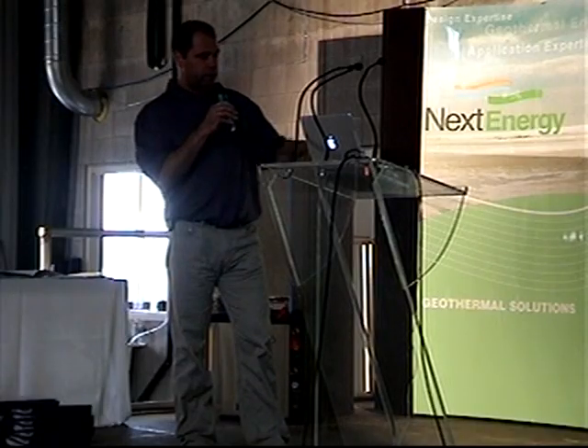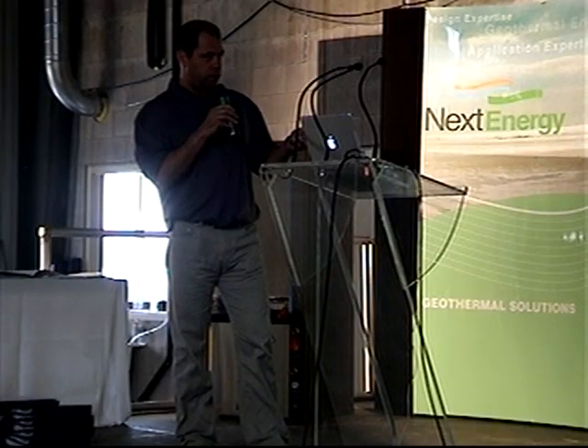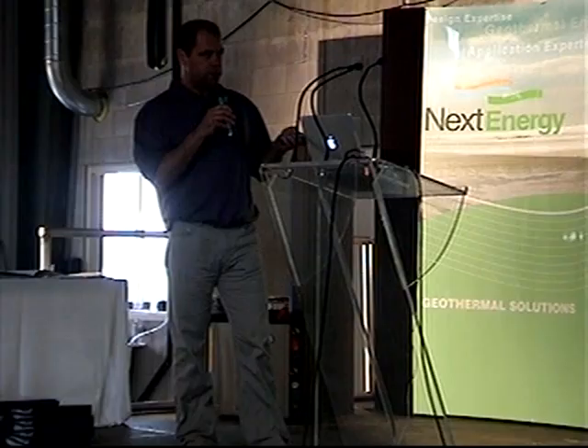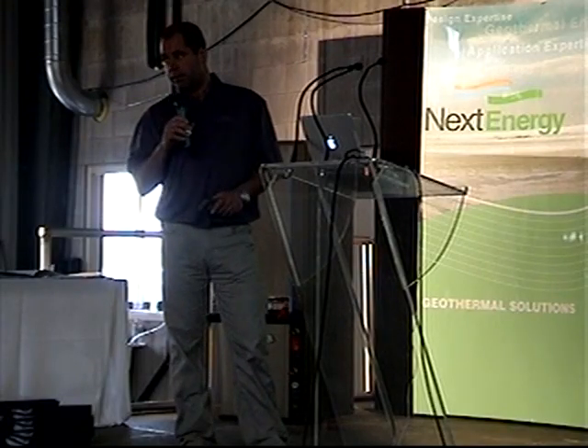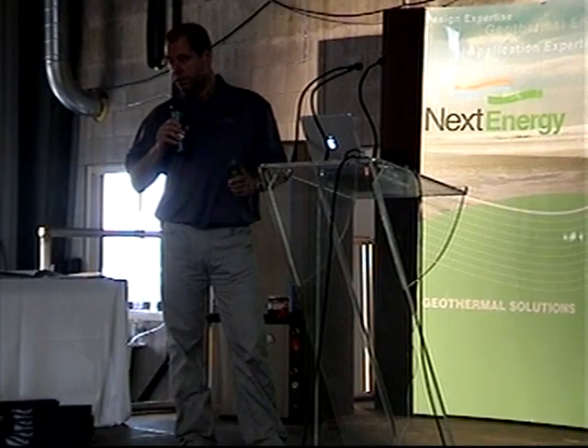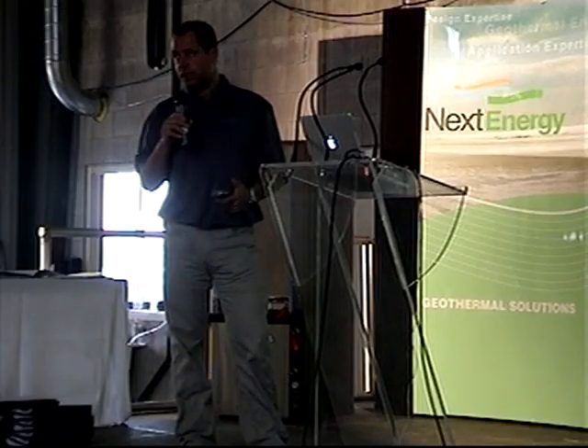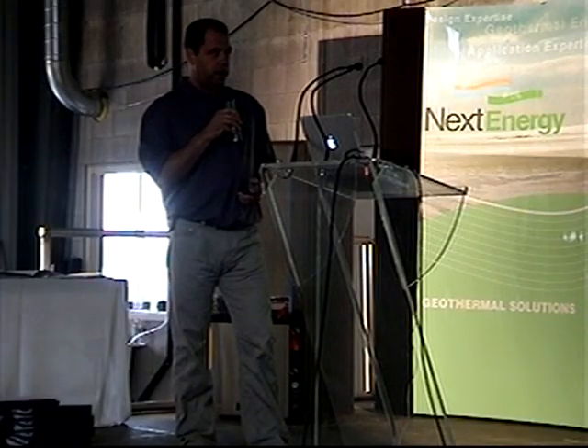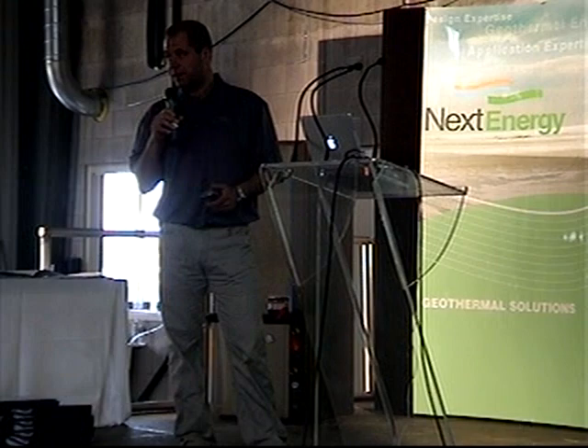And like I mentioned earlier, the POE oil is hygroscopic, and that's probably the most important thing you need to remember. Do not let any air or moisture get in that system. Always change the filter dryer, and work quickly. Do not leave that system open.